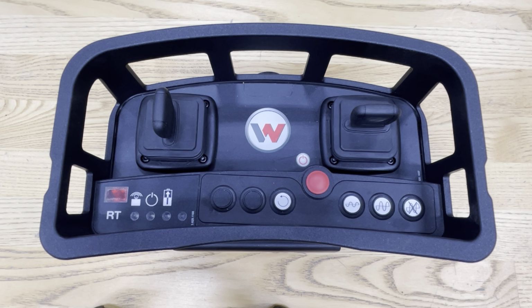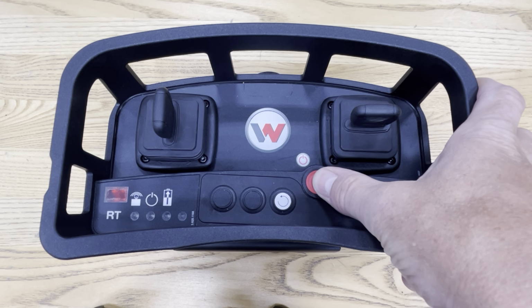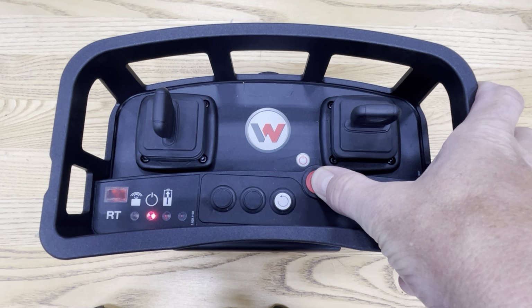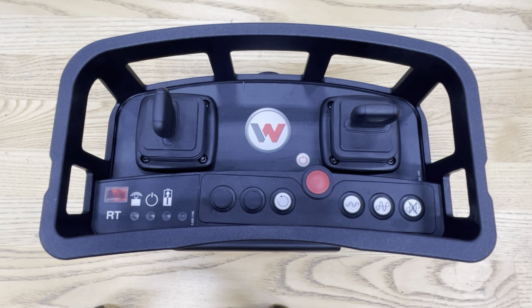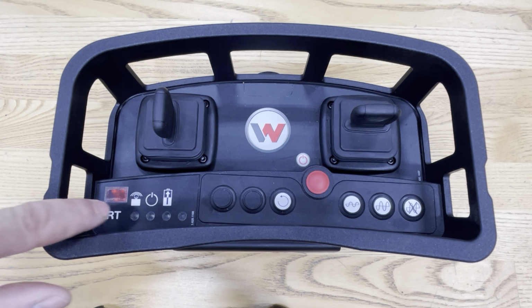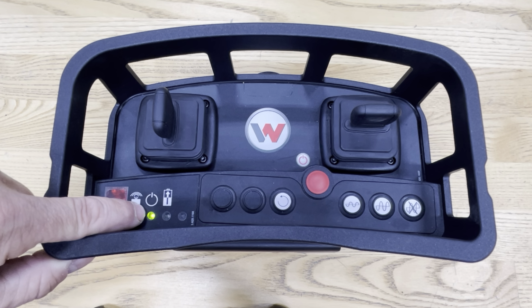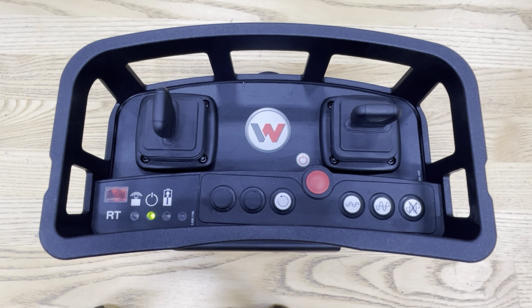To recalibrate the transmitter, we're going to power on the unit. Typically you will know when a transmitter is requiring a recalibration. The power lamp here will be a solid red, which is usually a good indicator that you need to recalibrate your transmitter. In this case, we're going to perform the function, just as an example.